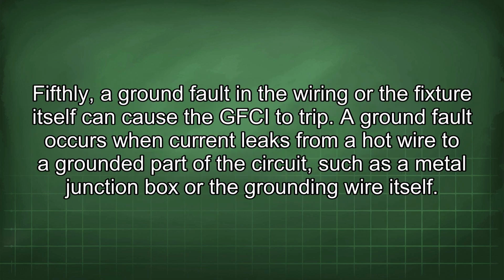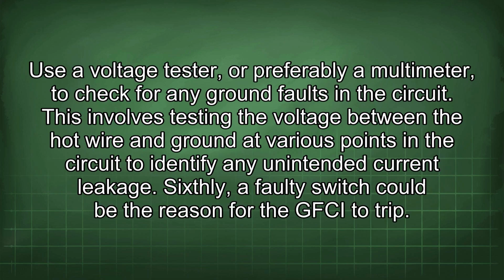Fifthly, a ground fault in the wiring or the fixture itself can cause the GFCI to trip. A ground fault occurs when current leaks from a hot wire to a grounded part of the circuit, such as a metal junction box or the grounding wire itself. Use a voltage tester, or preferably a multimeter, to check for any ground faults in the circuit. This involves testing the voltage between the hot wire and ground at various points in the circuit to identify any unintended current leakage.